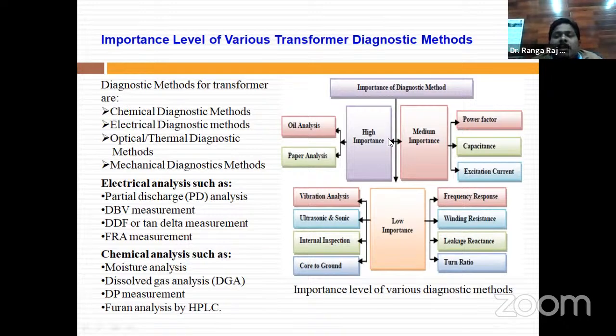Similarly, medium importance is given to power factor, capacitance, excitation current. Similarly, low importance we can give to basic tests - turns ratio test, leakage reactance test, winding resistance test, frequency response test. We generally perform these tests at the manufacturing stage.